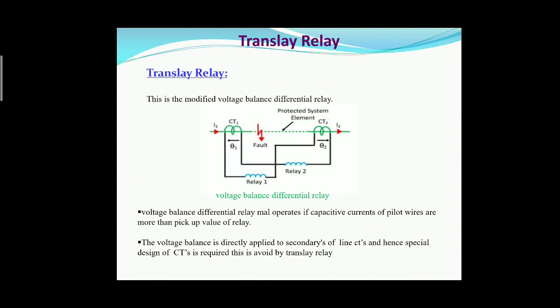But in the case of a voltage balanced differential relay, if the capacitive currents of the pilot wires are more than the pickup value, then the relay will maloperate. These disadvantages are overcome by using this translay relay. Okay, this is the construction and working of a translay relay.